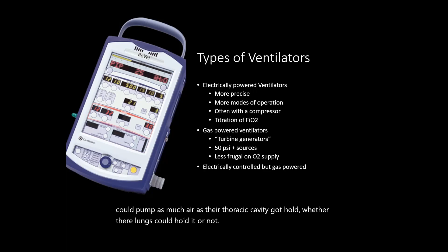So the very early ones weren't flow restricted. So if your tank was at 50 PSI, 60 PSI, whatever it was in your line pressure, that's what the patient got their inspiratory breath at. Shortly thereafter, the FDA realized that was probably causing some pneumothoraxes, and they were supposed to be regulated to 40 PSI or less, regardless of whatever's in the line pressure. But that's still a hell of a lot of inspiratory breath. And the bad thing about those is that most of them didn't have a pop-off or pressure relief valve, so you could pump as much air as their thoracic cavity could hold, whether their lungs could hold it or not.